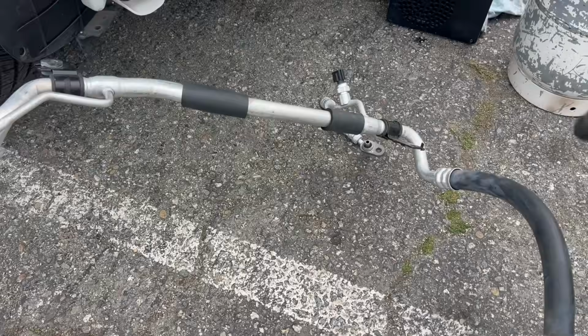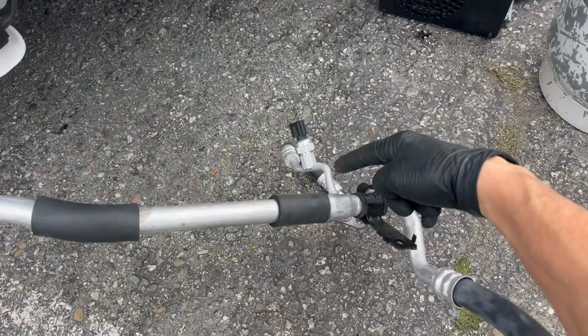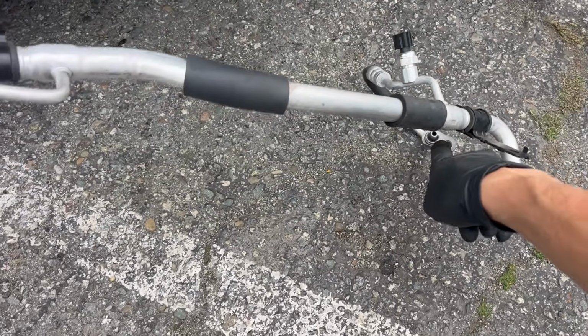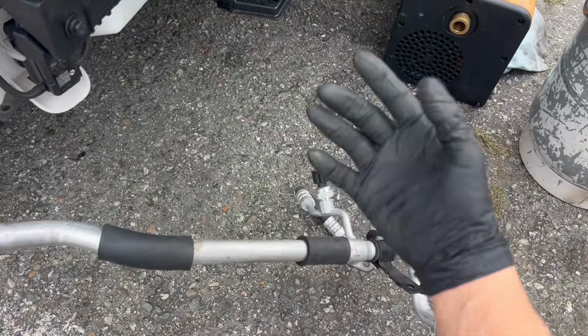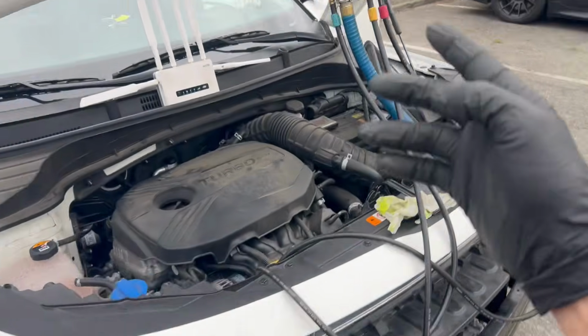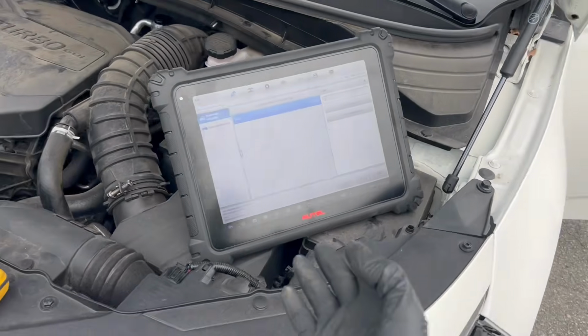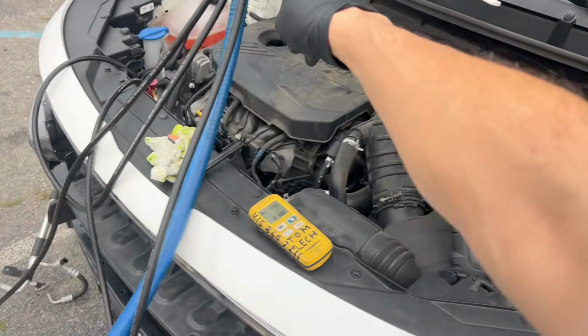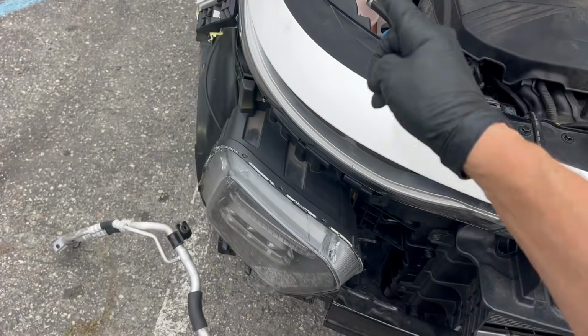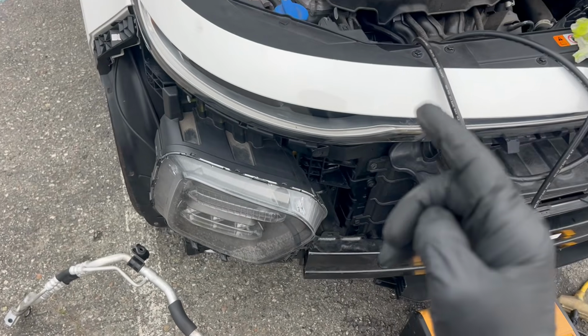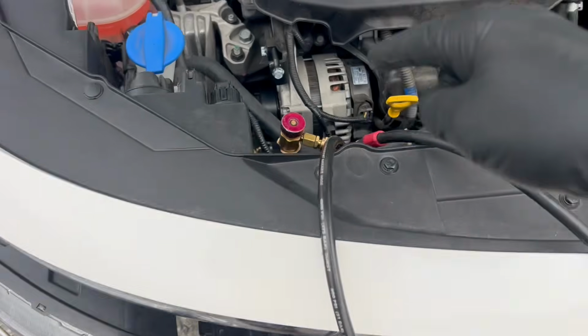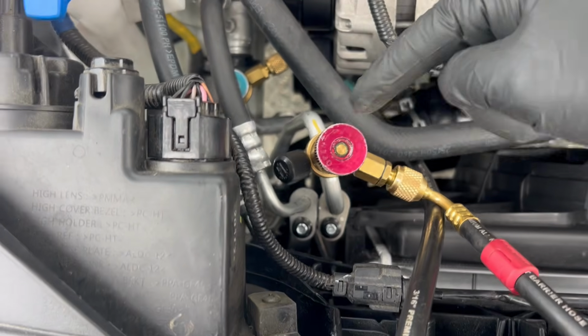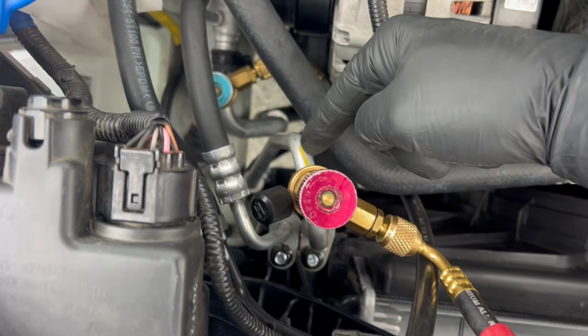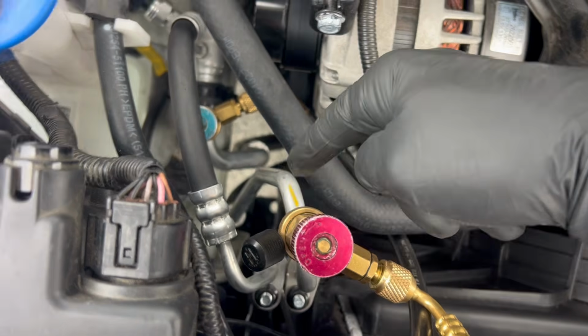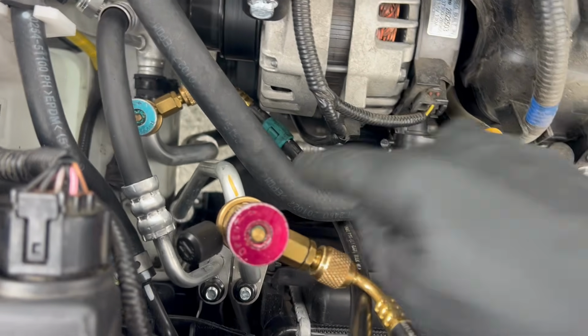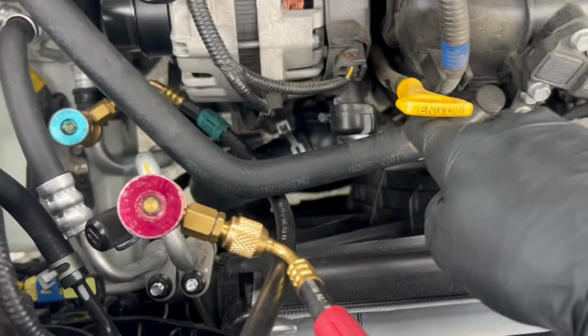So let's think of this. We have a transducer in the liquid line that comes off of the condenser, and through your, say you have your Autel. So here I have my Autel. I could be reading the pressure of the transducer, but let's say we had a collapsed inner lining in the high side. So here's the high side. This is the high side discharge. You see the liquid one right there? You see the discharge right here? You see that rubber hose that's going to the compressor?